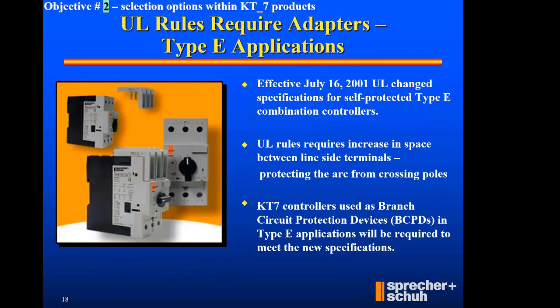One of the accessories that I kind of want to highlight, being that we're talking about self-protected type E, is that you really got to know how you're applying the product. And if indeed you're applying the KT7 using type E rules, UL gave us a redirect back in 2001 that says you guys need to kind of pad the line side or give it a 2-inch creepage space. So if you're going to use our device under type E rules, you're going to have to accommodate for some sort of 2-inch creepage space, in that if it's an individual circuit, you're going to need to use a KT7 something TE adapter piece that provides that 2-inch creepage space to where an arc from one pole can't reach over to the other pole.